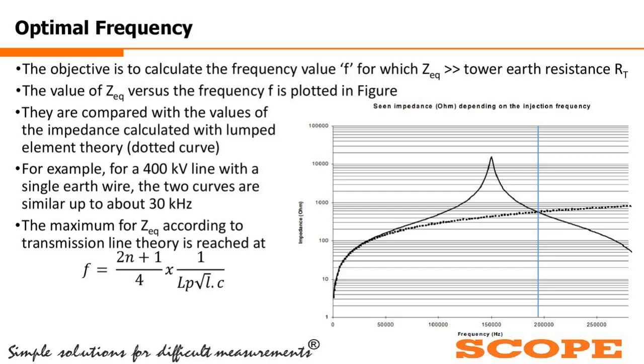So what they have concluded is that a frequency of 20 kilohertz or more can be used for the tower footing measurement, because in that zone, if we increase the frequency to that level, then this Z equivalent becomes very high with respect to the tower footing resistance. That's the reason the majority or all of the OEMs of tower footing resistance testers are talking about any frequency higher than 20 kilohertz, or to be more precise, they have almost finalized at 25 kilohertz. Some people are also using 30 kilohertz.